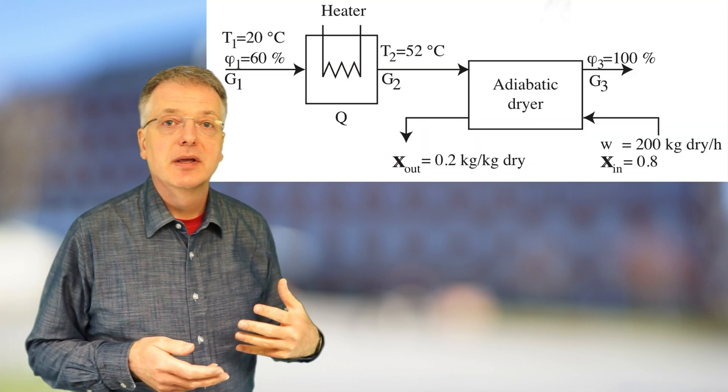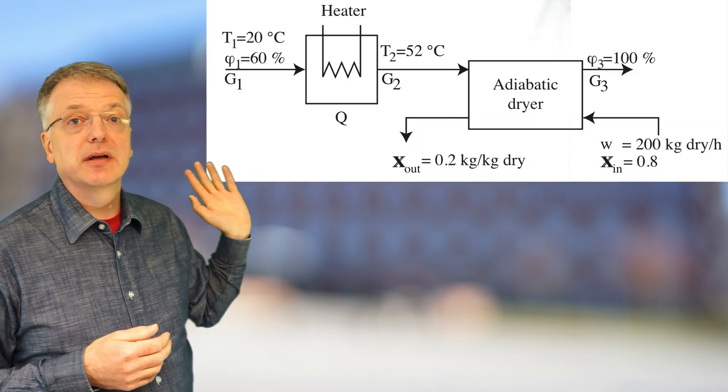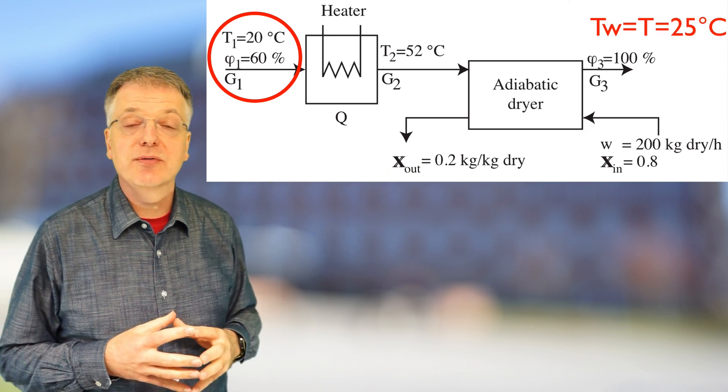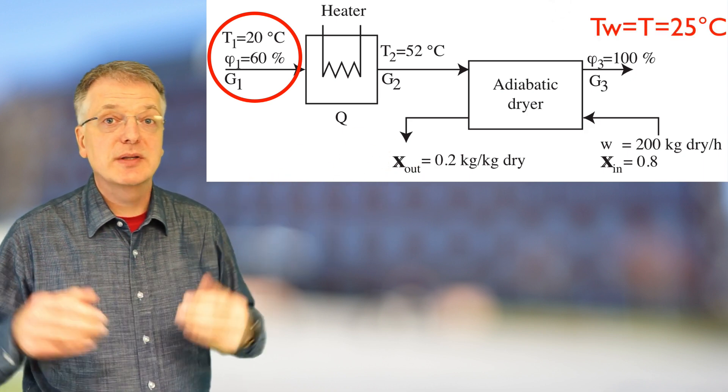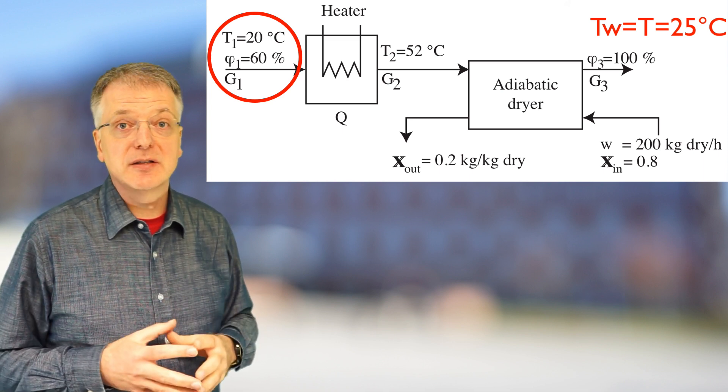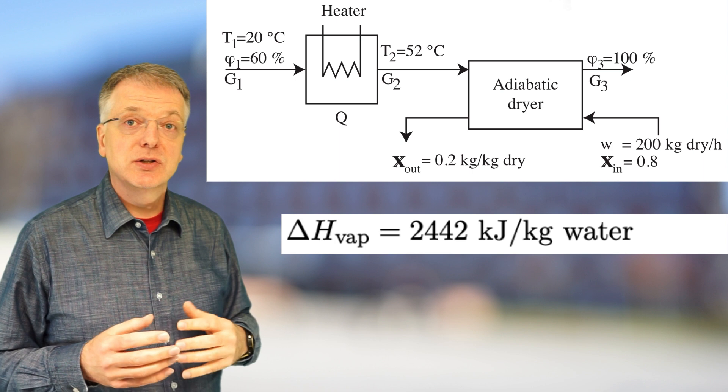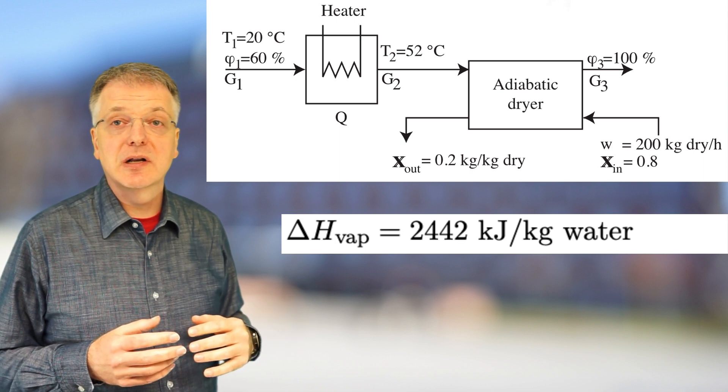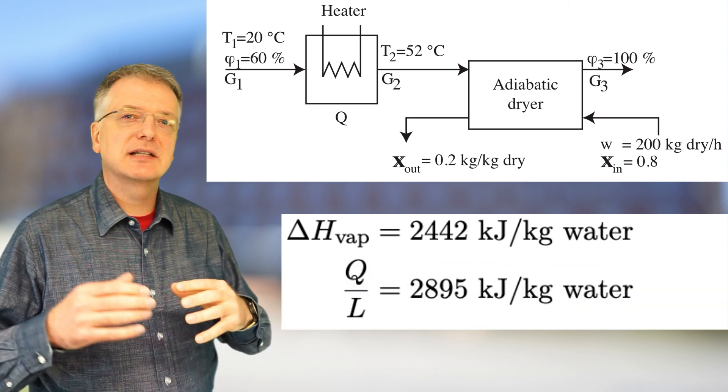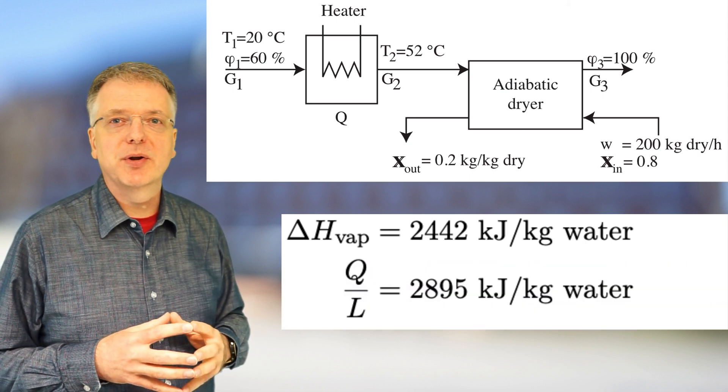To reiterate the task, we had an incoming fresh air at 20 degrees centigrade and an outgoing air with a temperature of 25 degrees and a wet temperature of 25 degrees. The evaporation enthalpy at 25 degrees is 2442 kilojoules per kilogram of water, but our calculations indicated we needed 2895 kilojoules per kilogram evaporated.